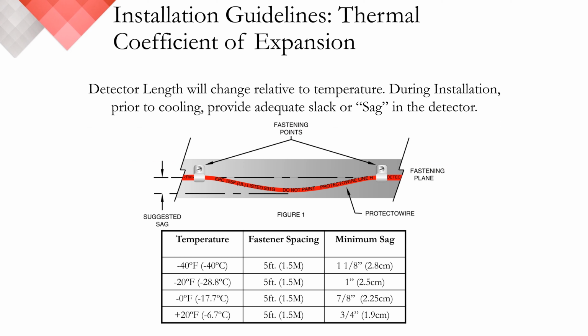Due to the thermal coefficient of expansion of steel, Protectowire linear heat detectors will expand and contract in length with changes in temperature. In applications where extreme temperature changes are expected, it's important to leave adequate slack in the conductor. This assures contraction of the detector will not put stress on mounting hardware or the detector itself. The table above shows the recommended slack or sag that should be introduced when installation occurs at an ambient temperature of 70 degrees.